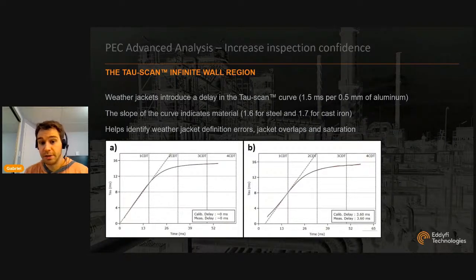So the infinite wall region, the first part of the A-scan, is going to provide you information on the weather jacket as well as the material. What we mean by the effect of the weather jacket is that typically aluminum, for example, is going to introduce a delay in the signal. So if you introduce an aluminum weather jacket over a component that didn't have one, you'll see that whole Tau scan curve shift to the right. The shape of the A-scan curve is going to be similar. You might see some effect right at the beginning, early in time, but most importantly, you get a shift to the right. And typically, you'll get 1.5 milliseconds of delay per half millimeter, or 20 thousandths of an inch, of aluminum. Stainless steel is going to have very little effect. It's not going to introduce a delay typically. And galvanized steel or carbon steel weather jackets are going to introduce some delay.